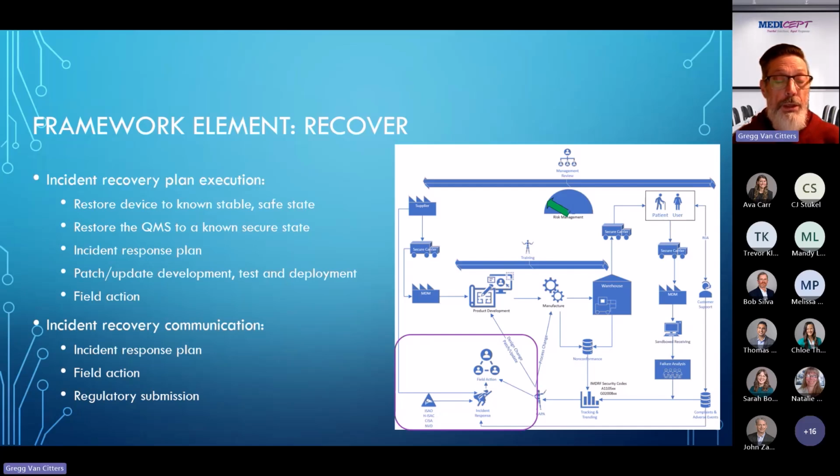Full recovery could be a longer-term process. Think prevention in the CAPA process. You may have to modify the device, maybe a design or process change. That could trigger another submission. But regardless, whenever you experience a cybersecurity event, you likely have to notify regulatory authorities anyway. But address the urgent security issues, especially those that put patient safety at risk, first, then notify.